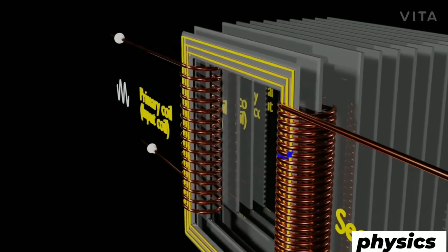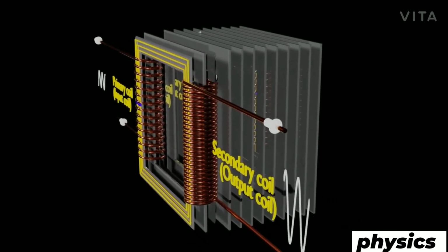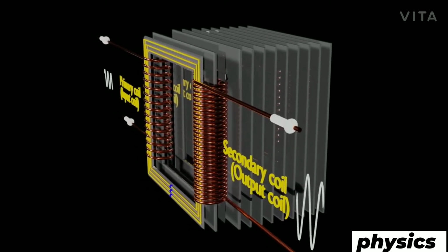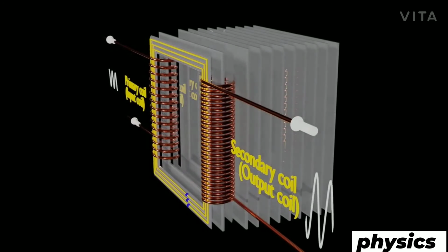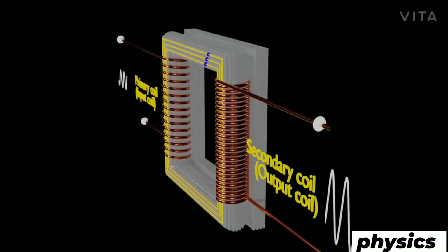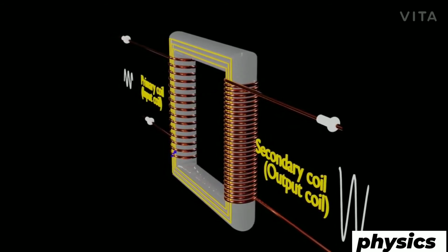But why are the layers laminated? Because of the changing magnetic field, eddy currents are induced in the conductive metal of a transformer core. The layers of insulation serve as a barrier to eddy currents, so eddy currents can only flow in narrow loops within the thickness of each single lamination.